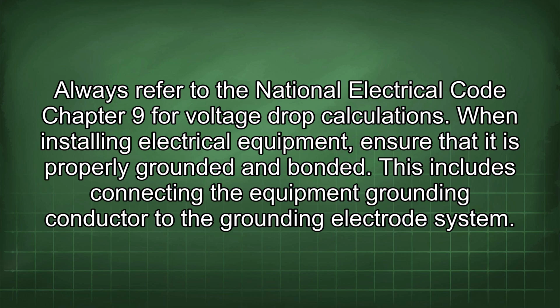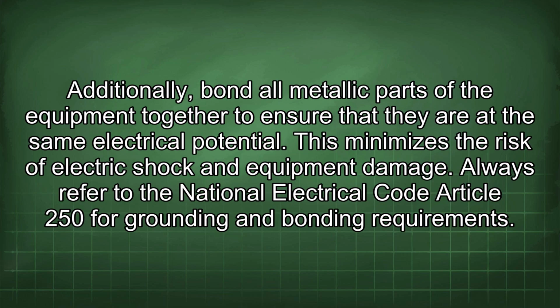When installing electrical equipment, ensure that it is properly grounded and bonded. This includes connecting the equipment grounding conductor to the grounding electrode system. Additionally, bond all metallic parts of the equipment together to ensure that they are at the same electrical potential. This minimizes the risk of electric shock and equipment damage. Always refer to the National Electrical Code Article 250 for grounding and bonding requirements.